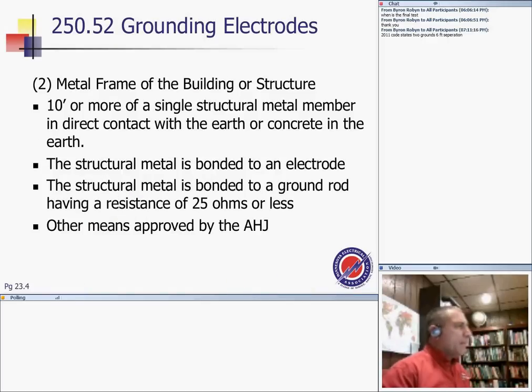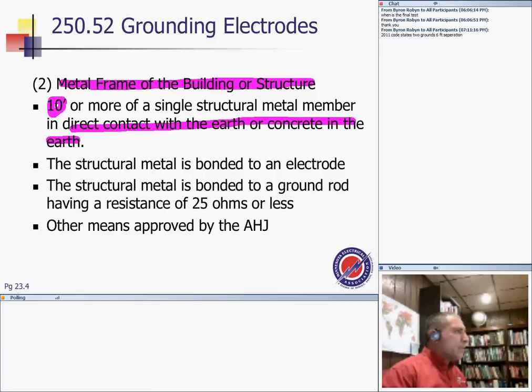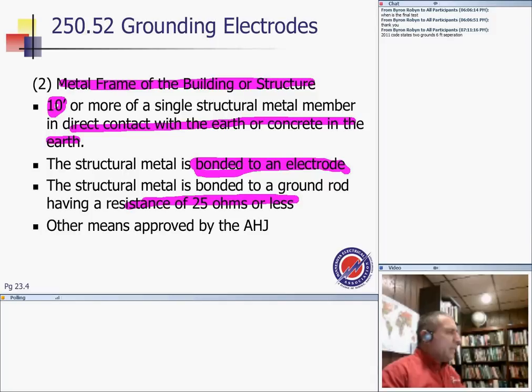Second, which is a well-respected standalone electrode system, the frame of the building or the structure. And they changed a few things. One or more structural metal members in direct contact with earth or concrete in the earth. So you have to be in direct contact with or without concrete for 10 feet. The structure is bonded to an electrode. In 2008, they changed it. 2011, they changed it slightly, guys. They said if you bolt to the foundation that acts as a ground electrode system, the structure is bonded to a ground rod having resistance of 25 ohms or less. Other means approved by the authority having jurisdiction.